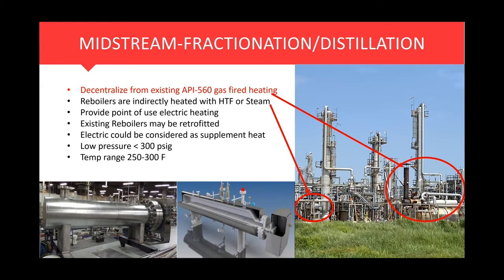And electric heaters, with SCR thyristor control, afford you 90% turn down in most flow conditions, and you only need to put in the heat input you need at the time. You don't have to have a 5 million BTU burner running if you only really need 1 million BTU or 500,000 for the moment. The electric heater can do 0 to 100% modulation of heat output into the process.